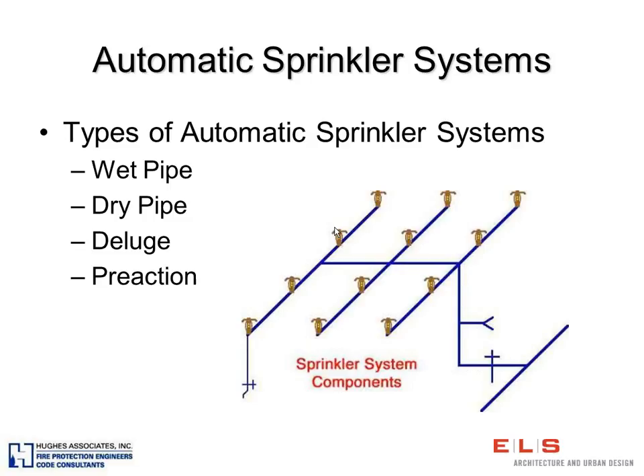There are four types of automatic sprinkler systems. Wet pipe, the kind we all think about, the kind you have in the office building maybe that you're sitting in right now. Here's your municipal water purveyor's line right here. You come in, there's a control valve, oftentimes a PIV, and then a fire department connection, and the pipe is wet all the way coming through here, and you come out to your sprinkler system where you have sprinklers that are protecting your space. All the pipe has water in it.